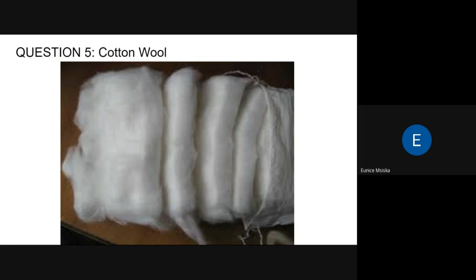Cotton wool also has a tendency to shed, so as the compressor pulls in air, there is a high possibility that cotton wool fibers may be drawn into the unit, causing obstruction in the air pathway and affecting concentrator performance. Eunice notes that she and Fatsani came across this exact situation in the field and invites Fatsani to share the experience.